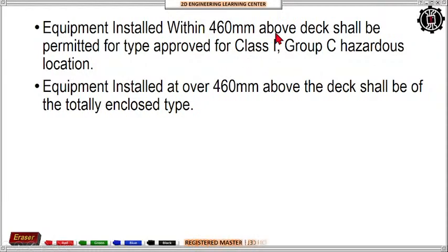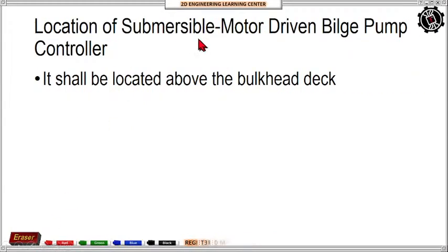Kasi ito kasing deck is open space, no? So, dapat yung ating equipment must be waterproof and corrosion proof or corrosion resistant. Equipment installed at over 460 mm above the deck shall be of totally enclosed type, no? So hindi lang water resistant, watertight, corrosive type, or corrosive resistant. Location of submersible motor driven bilge pump controller. So it shall be located above the bulkhead deck. No, itong submersible motor driven natin na pump controller.